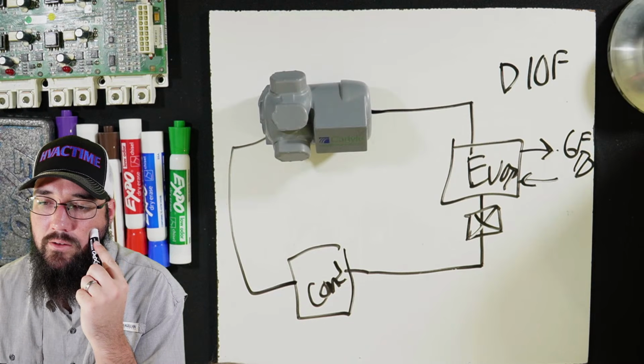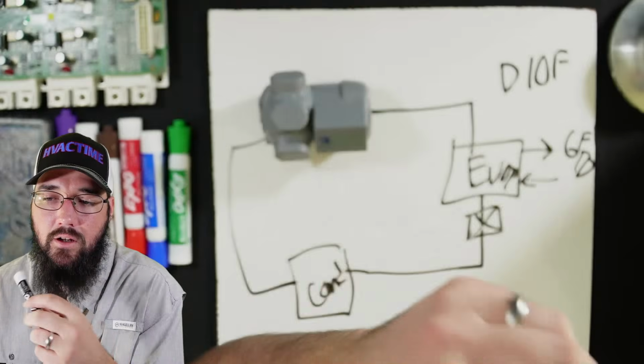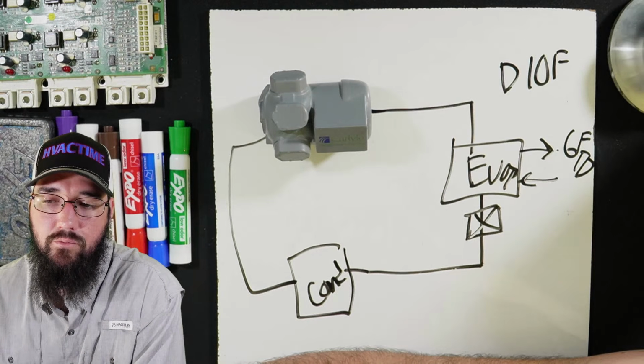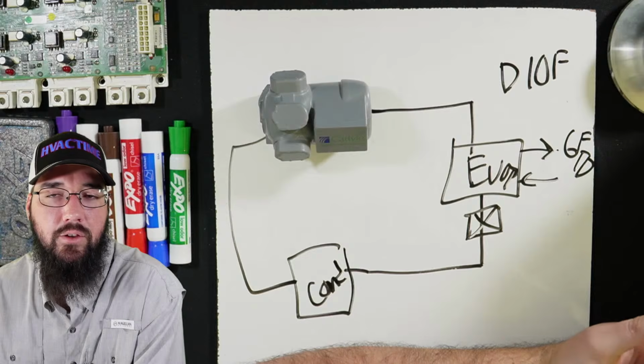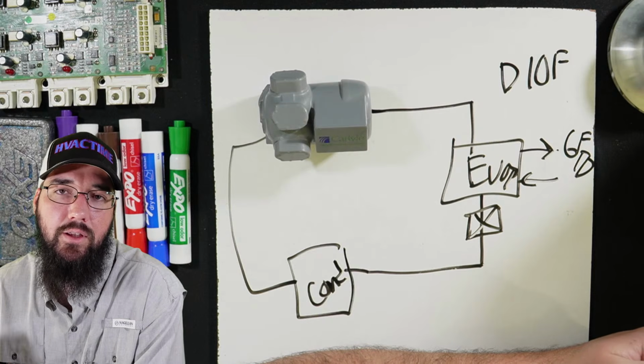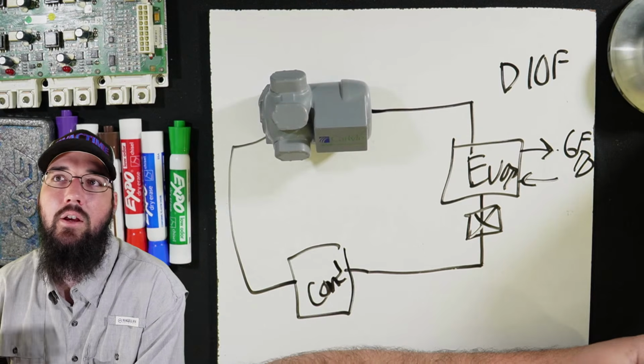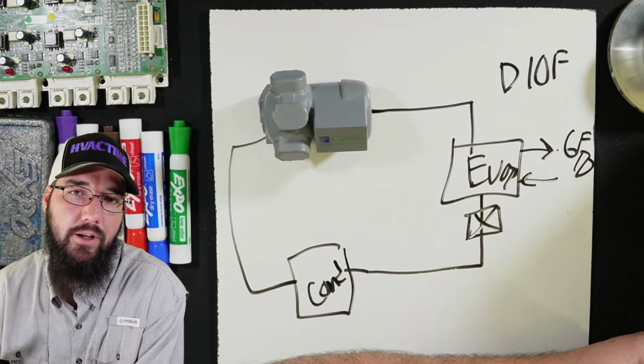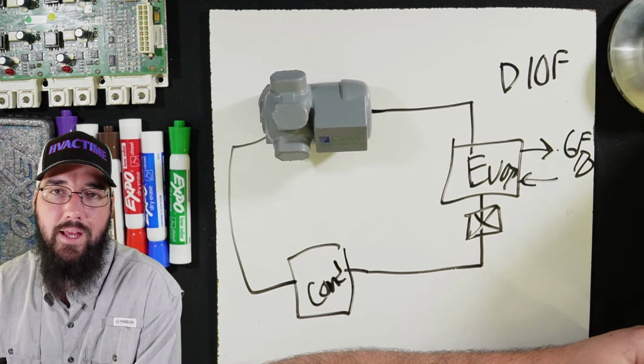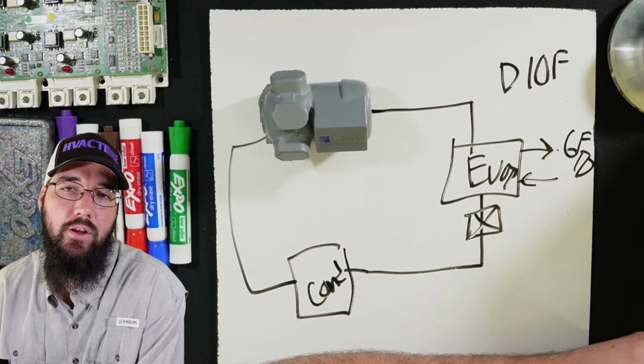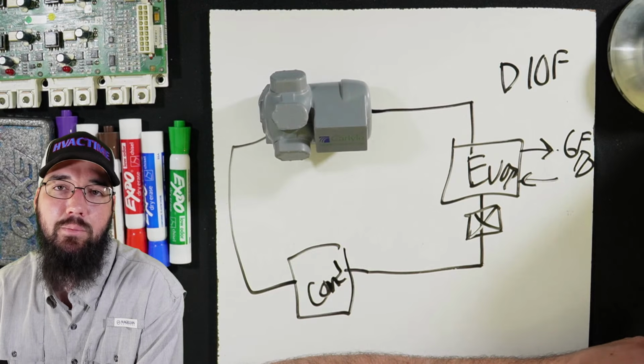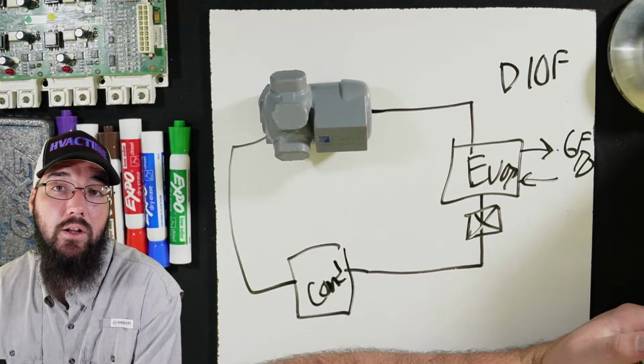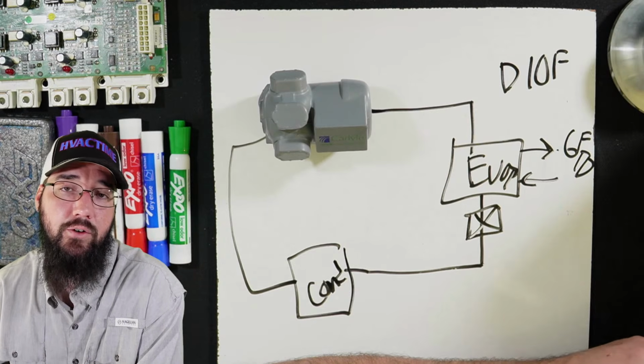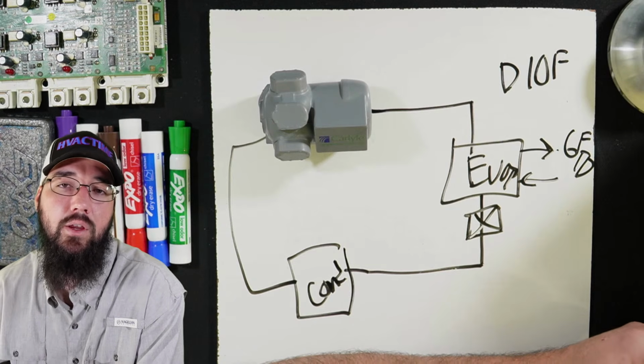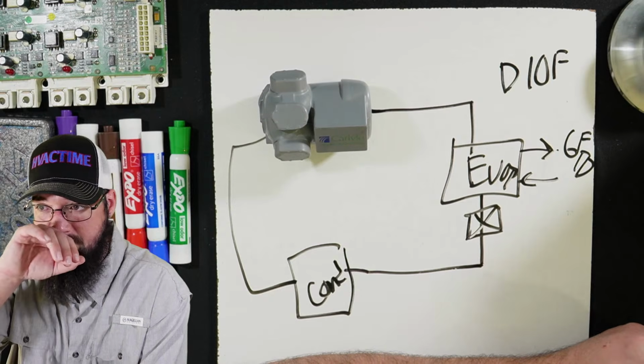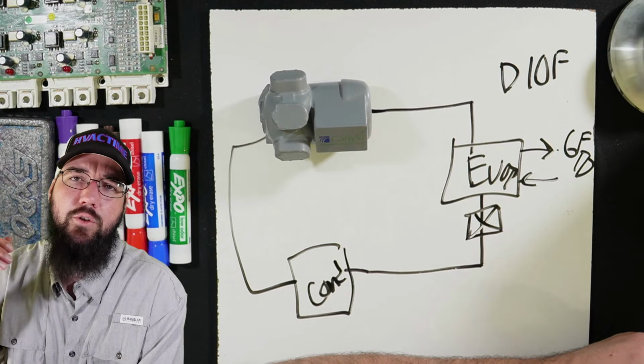Yeah, so high level, the eductor is a jet pump. The oil is getting migrated to the flooded or falling film evaporator, and we're getting that back. So you're familiar with a gas pump, Sterling. It's an alternative method to a gas pump. It's what everybody else does, and it's what Trane does on their centrifugals. They don't use gas pumps, they're using an eductor.